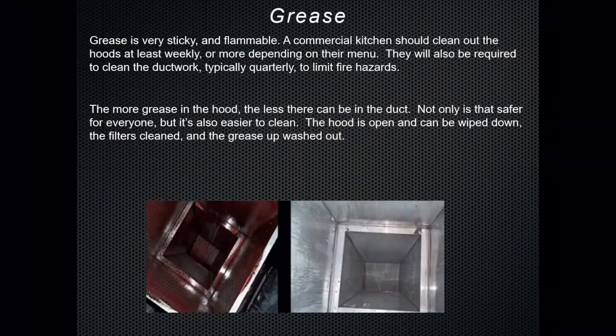That's because grease is so sticky and so flammable that you want to make sure that you catch it down in the kitchen. Some people will say it feels like I'm cleaning my hood too often. That's actually a good thing, and it means that they're working better than what they're used to, because that way you're not letting the grease go into the ductwork. It doesn't create a fire hazard. It isn't on the roof or on the cars in your parking lot.